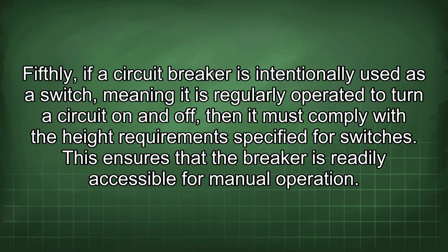Fifthly, if a circuit breaker is intentionally used as a switch, meaning it is regularly operated to turn a circuit on and off, then it must comply with the height requirements specified for switches. This ensures that the breaker is readily accessible for manual operation.